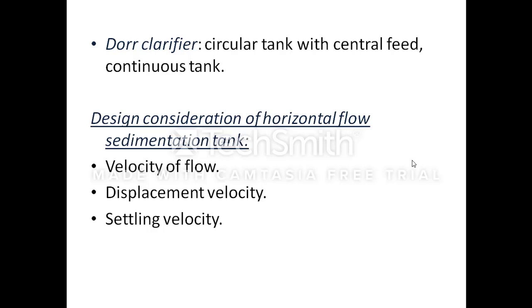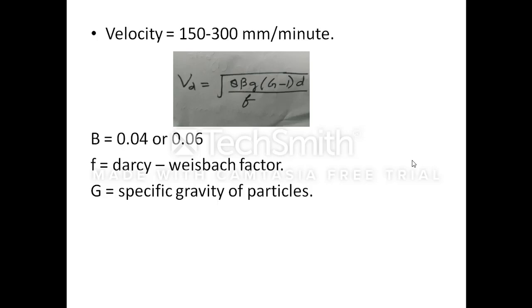For the design considerations of the horizontal flow sedimentation tank, the velocity of flow should be such that suspended particles can settle down. The velocity is generally taken as 150 to 300 mm per minute. According to Camp, the displacement velocity is given by: Vd = √(8β·g(G−1)·d / f), where β = 0.04 or 0.06, f is the Darcy-Weisbach factor, and G is the specific gravity of particles. The velocity must be such that settled particles are not lifted back up.